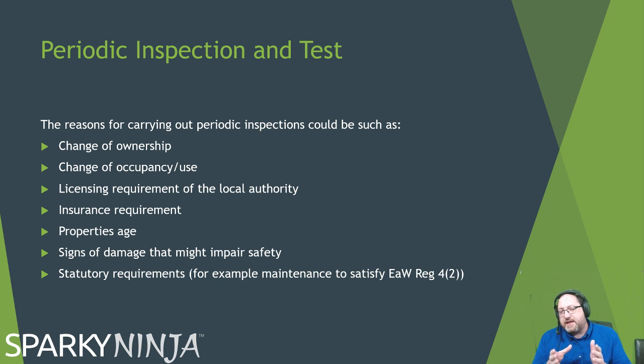Periodic inspection and testing isn't covered in the 2392, it's mainly on the initial verification. But it's important to know why periodic inspection and testing is carried out, so you know when to go on to that other area of work, and you may be challenged on that in the assessment. So the causes or the needs for periodic inspection and testing, these are the common examples here: changing of ownership, changing of use, occupancy of a building, licensing requirements of local authorities, insurance, property age, etc. What you mustn't ever put down on a periodic certificate is requested by the client. Periodic reports are never done because they were requested by the client. They're done for a purpose, and we need to make sure we know what that purpose was.